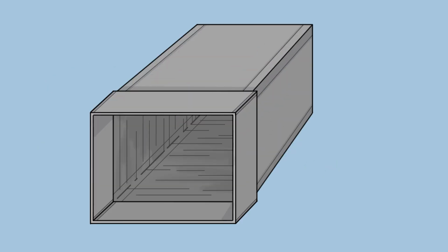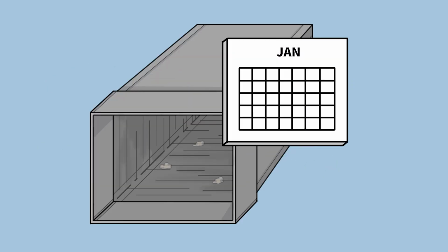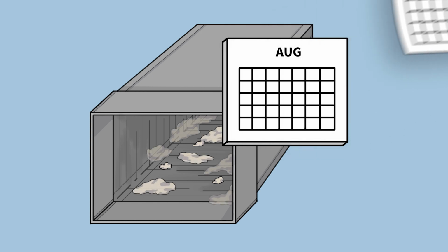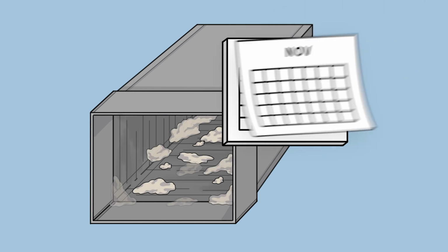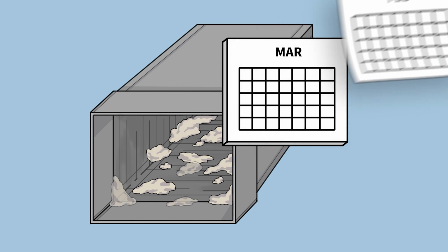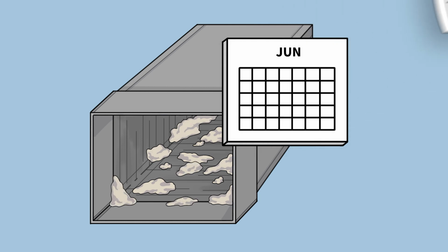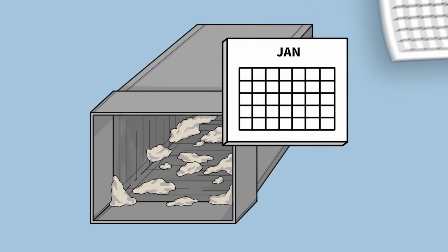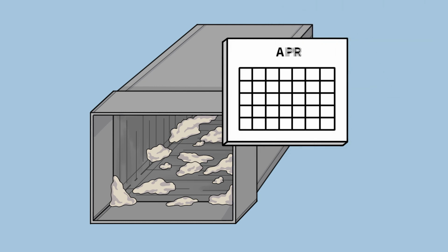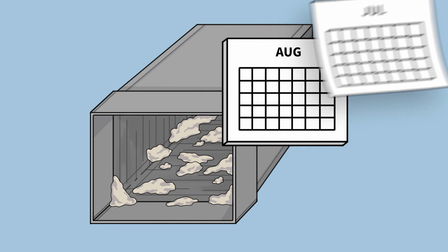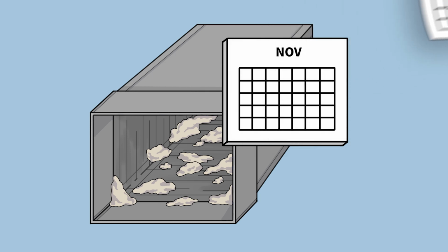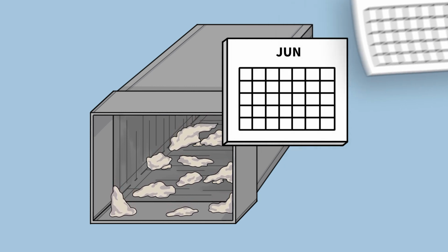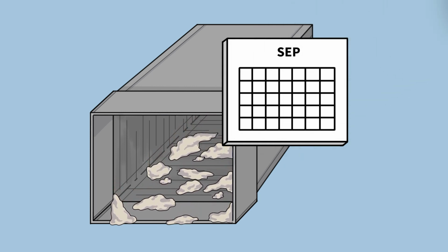Additionally, the inside of ductwork is not completely smooth, and over time, dust, dirt, and germs gather and settle on inside surfaces of ductwork, particularly at joints and bends. The increased airflow and pressure created by connecting a positive pressure fan to existing return ductwork will disrupt particles that have settled over time. Without proper planning, this increase in airflow and pressure will push the dust, dirt, and germs into other rooms connected to the HVAC system.